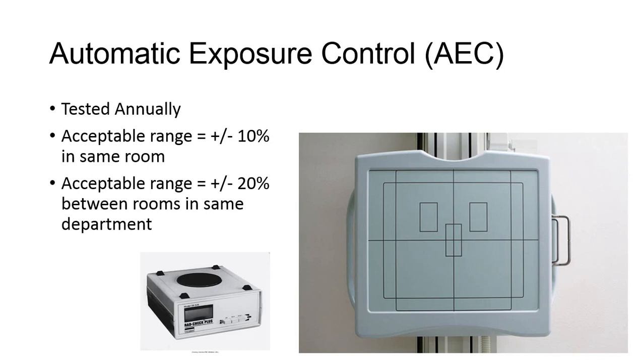Automatic exposure control should be monitored for repeatability. Your textbook suggests five exposures should be taken at the ion chamber to measure the output. The same test should be performed at various density settings when using AEC as well. This should be checked annually with acceptance limits plus or minus 10% within each radiographic room, but with a noted 20% variance is acceptable when comparing different rooms within the same department.